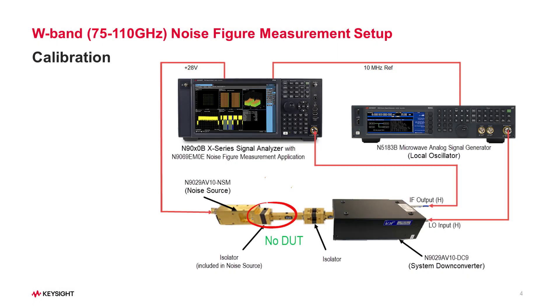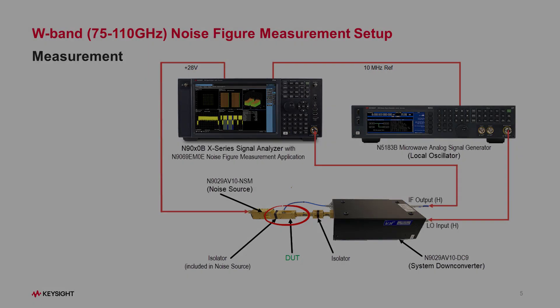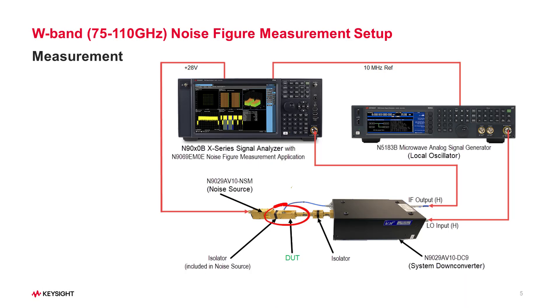To perform the calibration, connect the noise source directly to the RF input port of the System Down Converter. Calibration is done without the DUT in place to measure the noise figure contributed by the equivalent instrument.